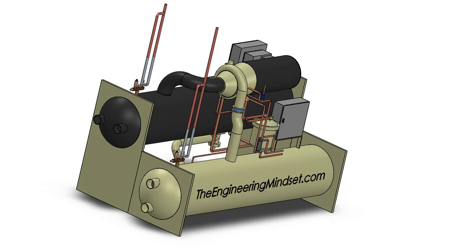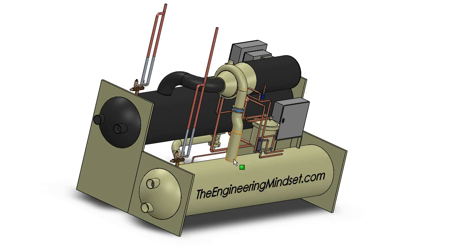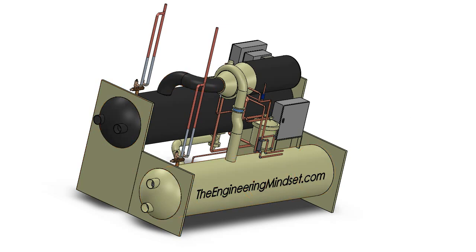From the other videos in this series on chillers, you should know by now that the refrigerant always flows from the evaporator into the suction line, through the compressor, down the discharge line, into the condenser. It does this so that the chiller can dump the unwanted heat collected from the building in the evaporator and move that into the condenser so it can be sent off to the cooling towers.